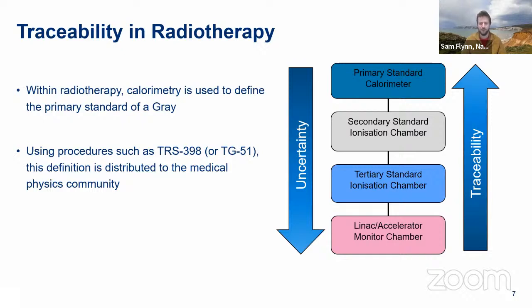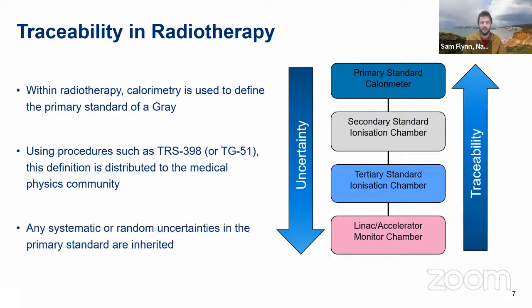They're very similar, with minor tweaks and differences, but the overall premise is the same of how you go from a standards lab to using the clinic. Because you have this chain of calibration, one measurement is dependent on the other. Any uncertainty at the primary standard level is inherited by everyone else down the chain. So if the primary standards lab has a 5% uncertainty, by the time it's used in the clinic, you have a 5% plus whatever else is added in the chain. So it is really important for us at the primary standard level to minimize that as much as possible, to give the best quality care we can to a patient at the end of the chain.